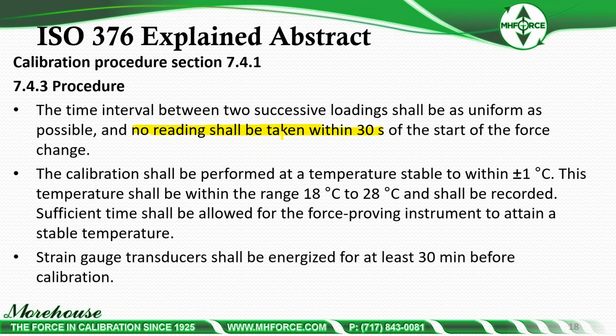And if you're sending your equipment to a lab that's just going up and going down and they're not waiting 30 seconds, they are not following the ISO 376 standards. So the other part of the standard: the calibration shall be performed at a temperature stable to within plus or minus 1 degree C. This is the same as E74. This temperature shall be within the range of 18 degrees C to 28 degrees C and shall be recorded.